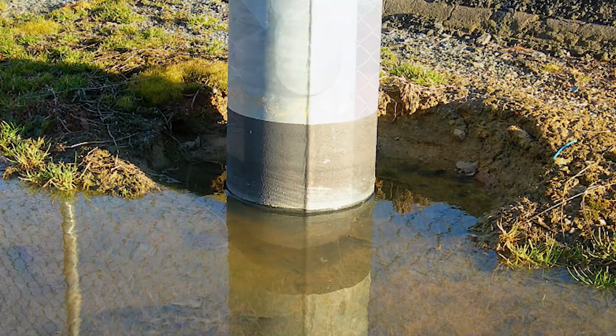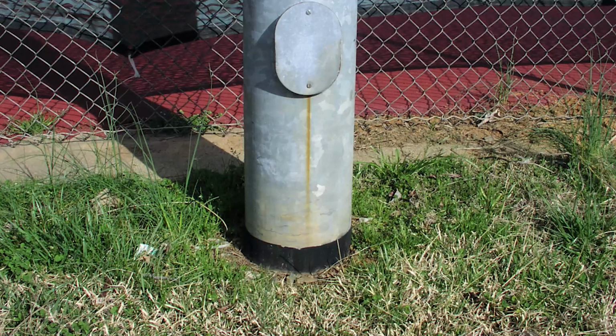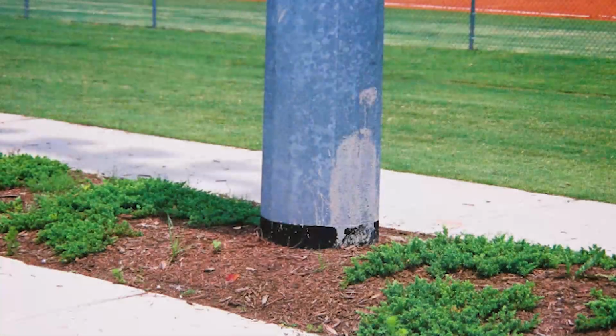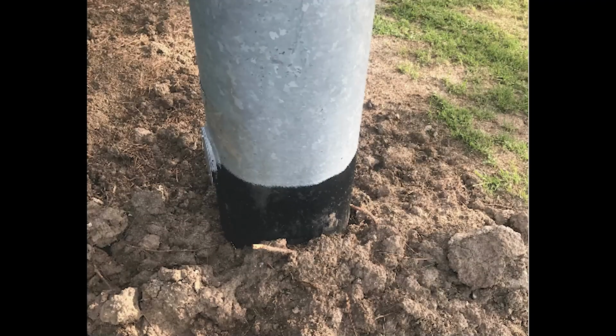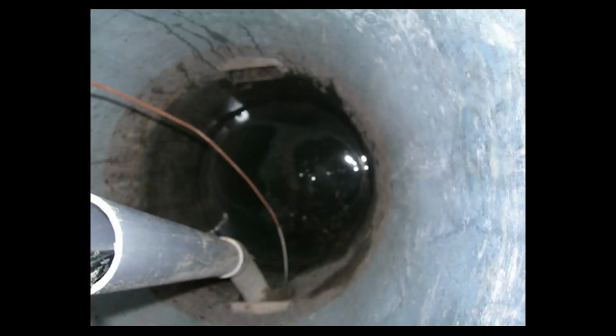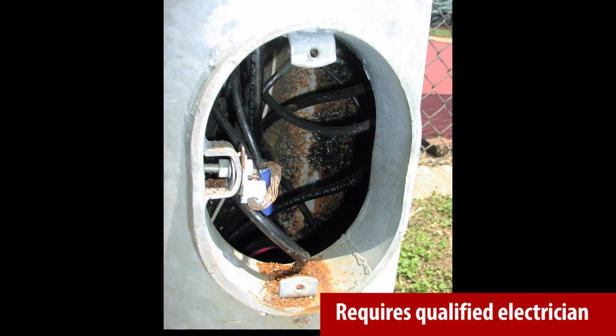Some direct buried steel poles feature a protective mastic coating just above and below grade at the base where the pole enters the ground. For these, you'll want to make sure there's the proper amount of mastic coating above grade and outside of the pole to ensure no corrosion or pitting of the galvanized coating is occurring. It's also important to inspect the inside of the pole at or below ground level for any signs of corrosion. You can visually check by scratching some of the dirt back from the base of a direct buried steel pole and look for pitting, rust, and missing galvanization or mastic coating. Take the handhole cover off and inspect the inside of the pole to ensure there is coating present at a height located above groundwater and that there is no corrosion.